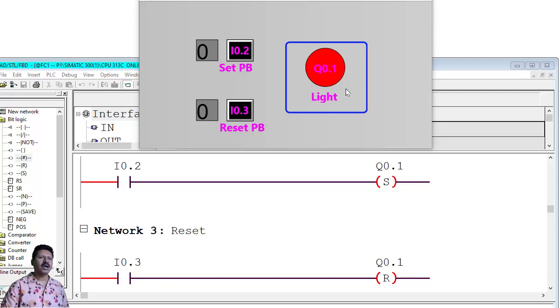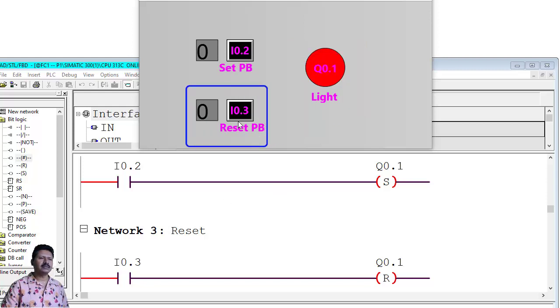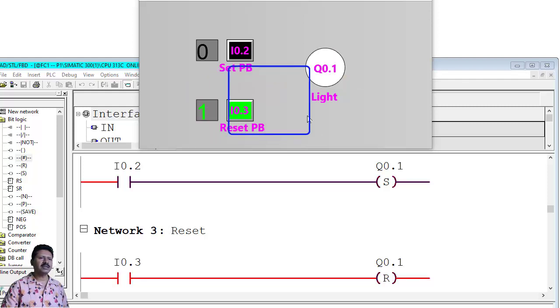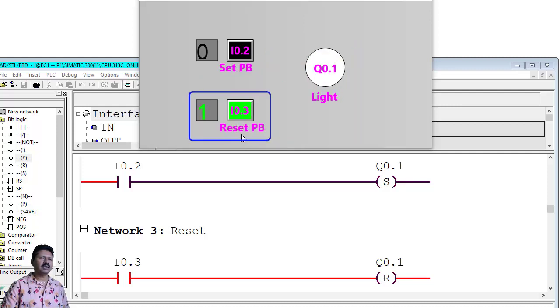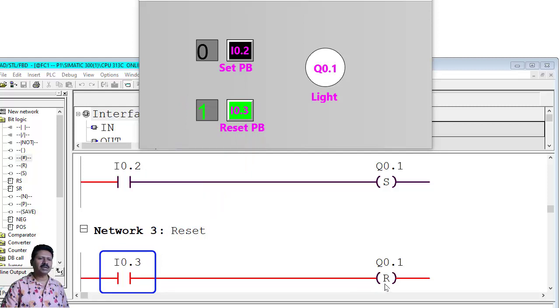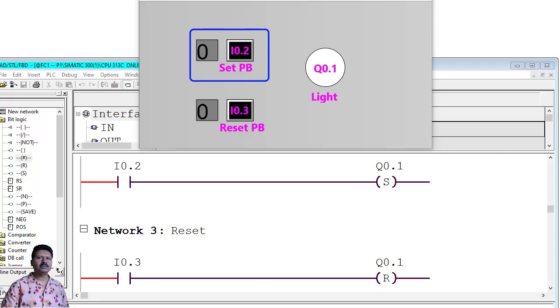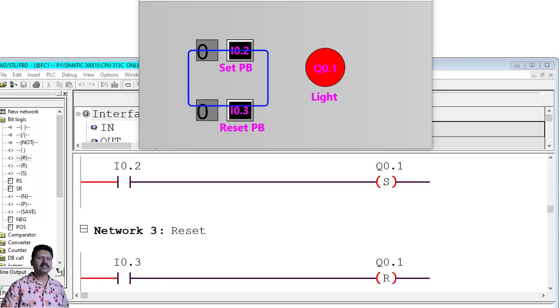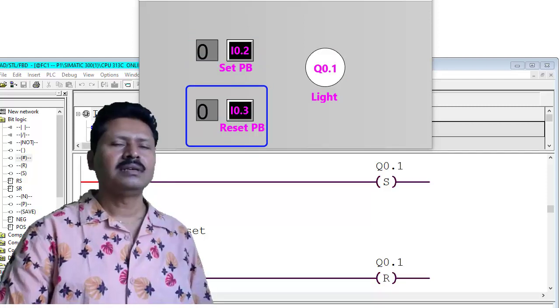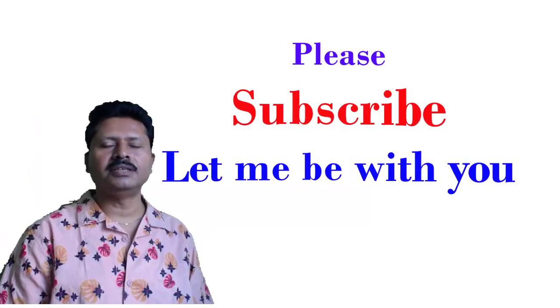This on condition will remain — the light can only be turned off by pressing the reset push button I0.3. Now pressing reset push button I0.3 to make the light off: yes, I press I0.3 and the light is off. I0.3 gives logic 1, the reset operation executes, and Q0.1 becomes logic 0 — the light is off. Again demonstrating: pressing set, releasing, then pressing reset, releasing. This is how we can use latching operation in ladder logic programming.